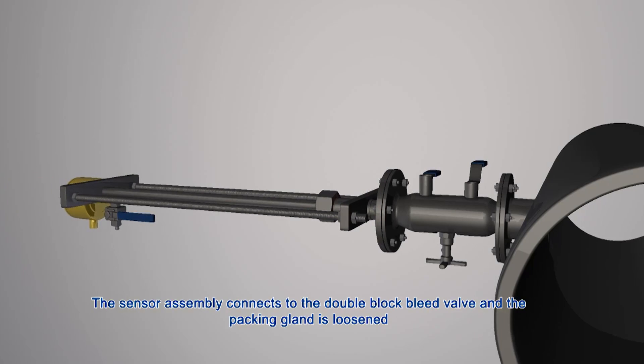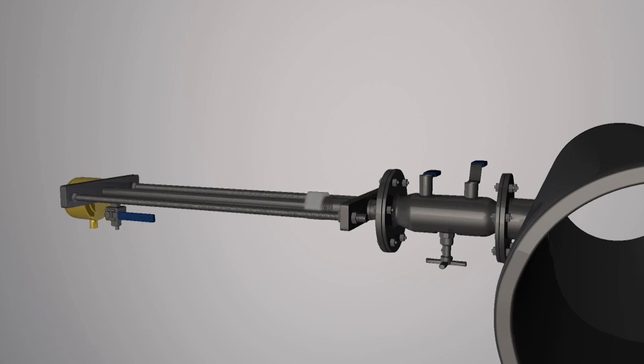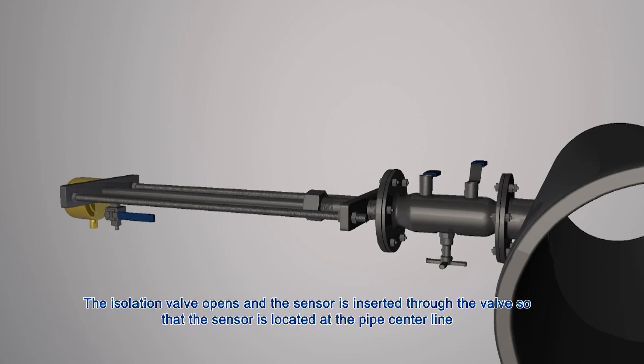The sensor assembly connects to the double block bleed valve and the packing gland is loosened. The isolation valve opens and the sensor is inserted through the valve so that the sensor is located at the pipe center line.